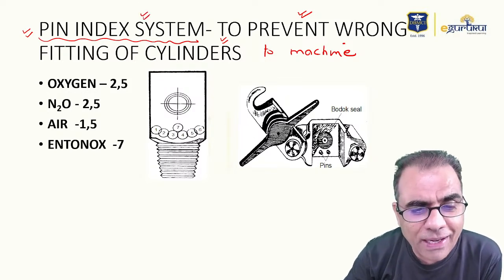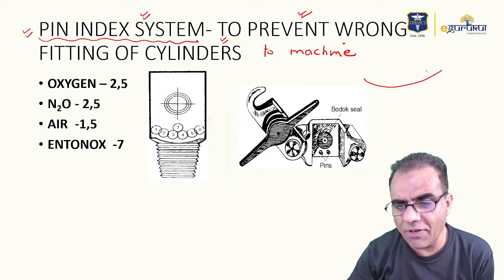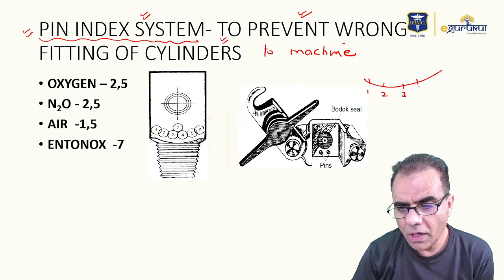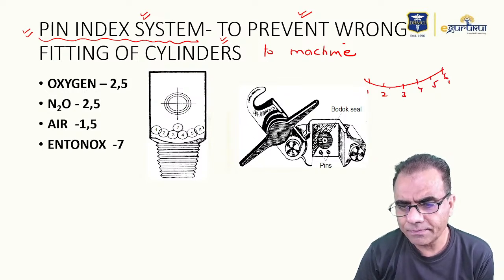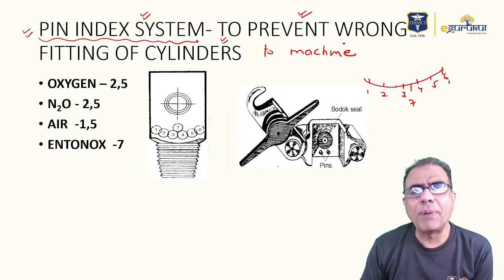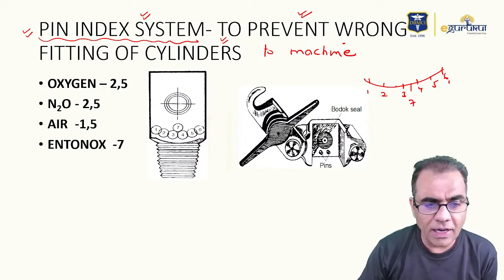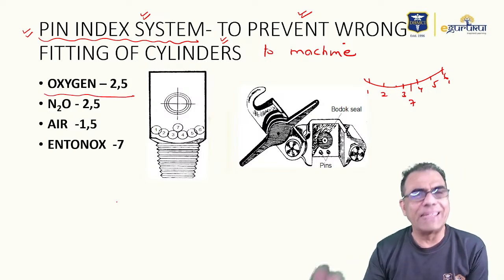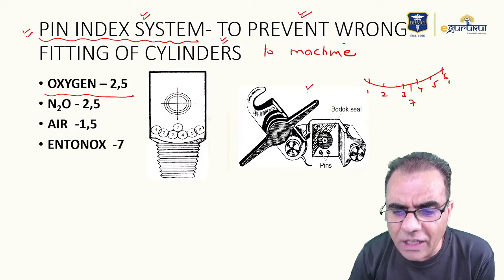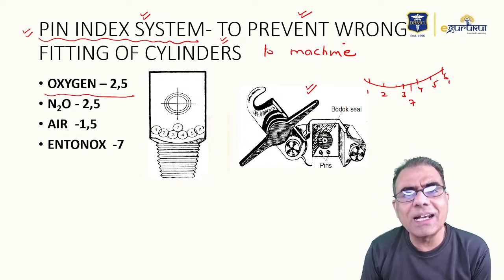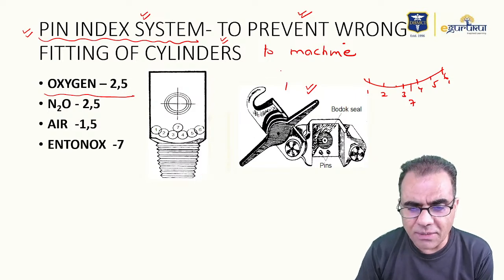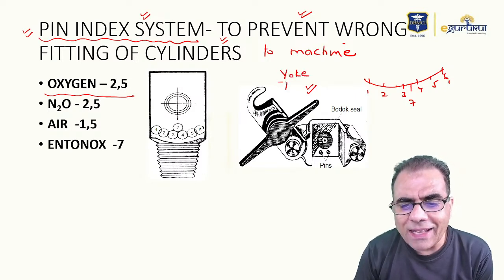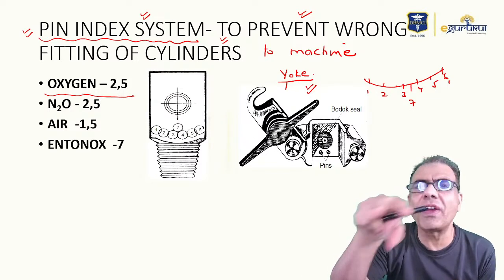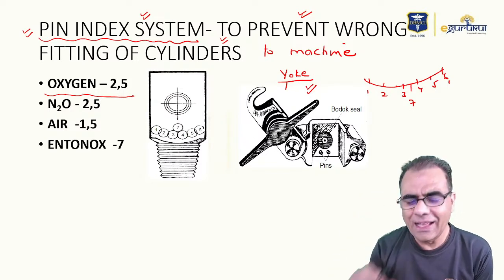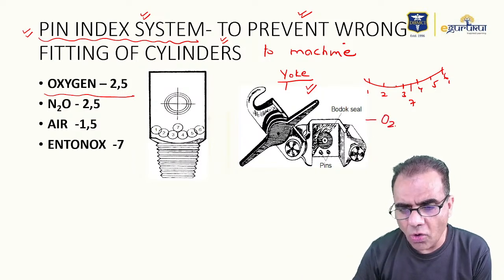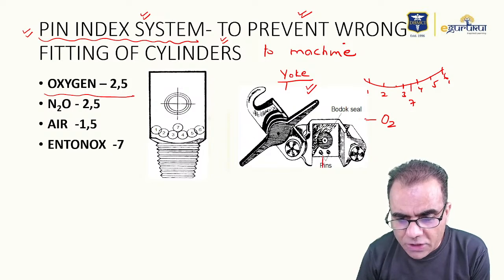They have devised 7 pin positions: 1, 2, 3, 4, 5, 6, 7. The pin index for oxygen is 2,5. What does that mean? The part of the anesthesia machine where cylinders are fitted is called the yoke. At the yoke, there are two specific defined positions for each cylinder. Say, for example, this is the yoke of oxygen. The positions of these two pins are 2 and 5.